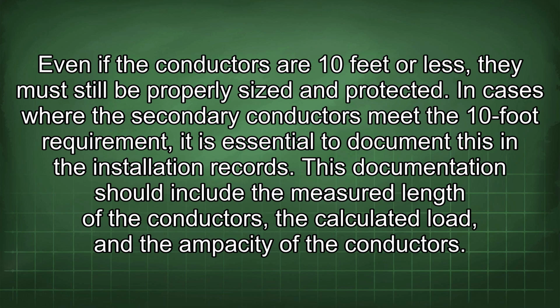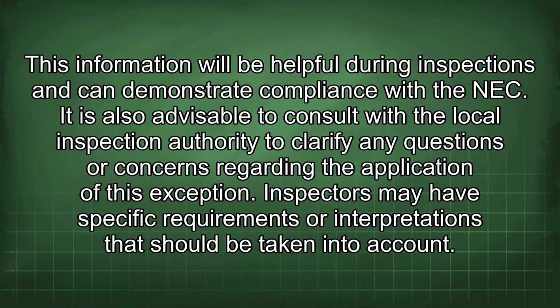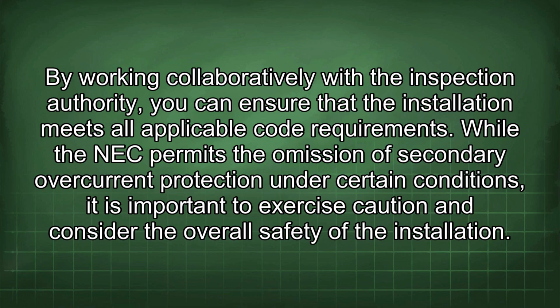This documentation should include the measured length of the conductors, the calculated load, and the ampacity of the conductors. This information will be helpful during inspections and can demonstrate compliance with the NEC. It is also advisable to consult with the local inspection authority to clarify any questions or concerns regarding the application of this exception. Inspectors may have specific requirements or interpretations that should be taken into account. By working collaboratively with the inspection authority, you can ensure that the installation meets all applicable code requirements.